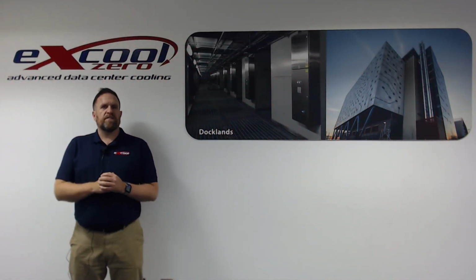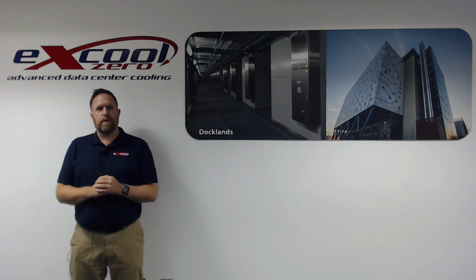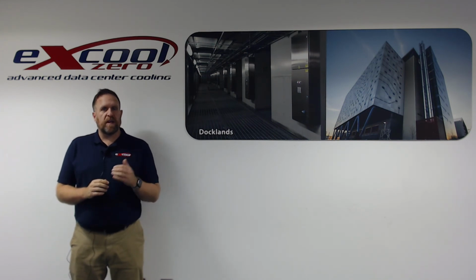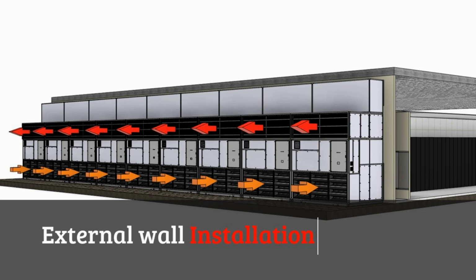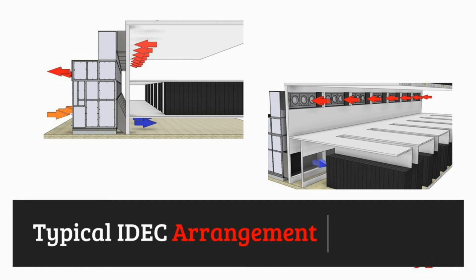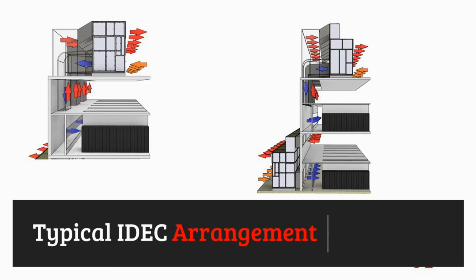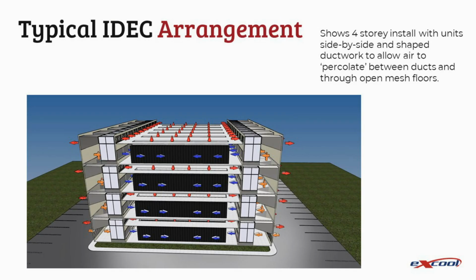The Excool Zero comes to site as a packaged unit with no site assembly required. This reduces installation time and also costs. The Excool Zero is the lowest in class operating weight, which will result in lower structural associated costs. In addition, the reduced size of the Excool Zero unit has resulted in a 20% increase in installed density. We can now provide up to 90 kilowatts per linear metre of perimeter wall. And a higher density means a higher ratio of revenue generating space versus support system space allocation.